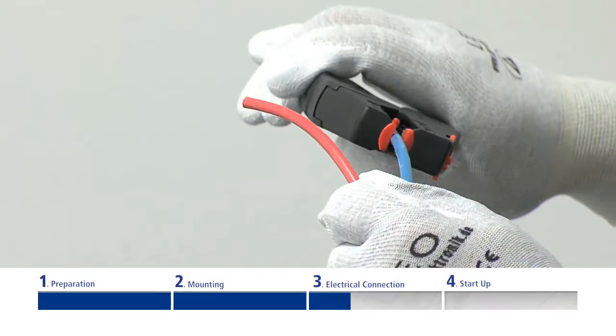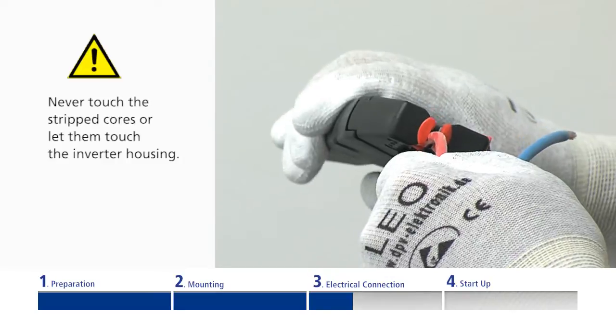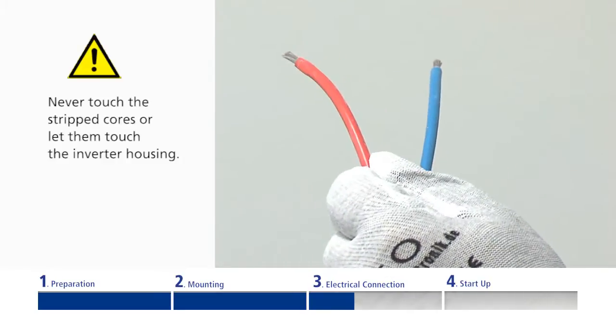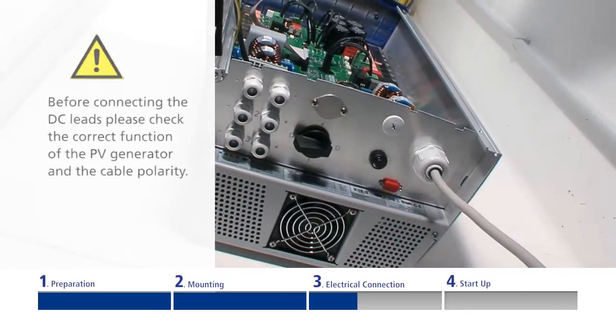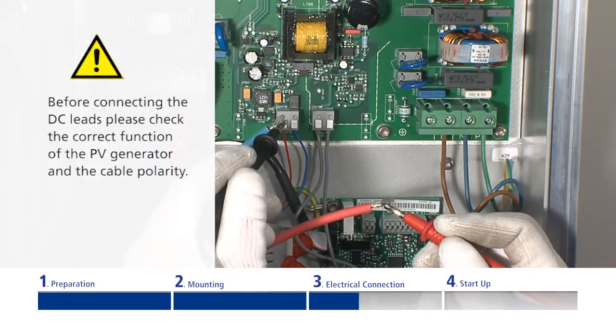Afterwards, the DC lead of the PV generator is connected. Ensure that the integrated DC disconnector is switched to the off position. Check the polarities with a measuring gauge.